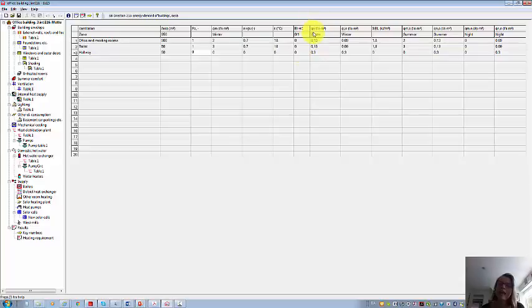Then we have the natural ventilation here. And the natural ventilation is the infiltration, so that's all the small gaps that we have in the building. And in the daytime, it's 0.13 because we open up windows and doors. And therefore, we have here the QIN, and that's infiltration in nighttime. And that's smaller than in daytime because we do not open up windows and doors in the night.